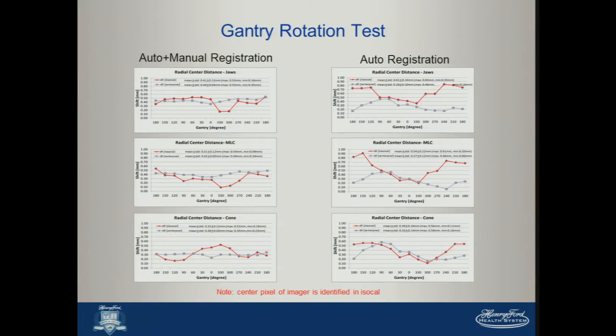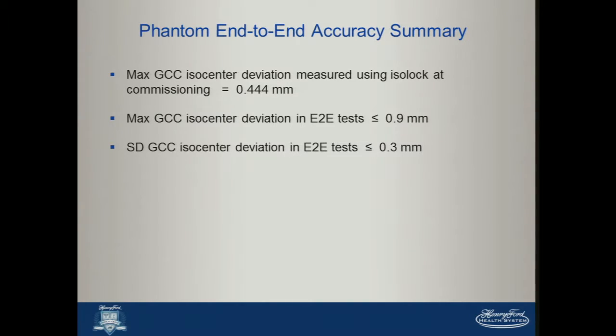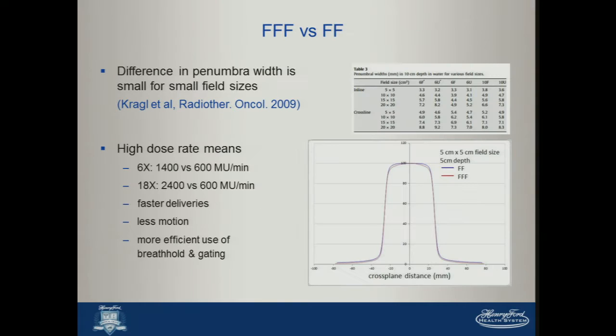So the end result is that we had at commissioning and continue to maintain pretty tight specs on this particular delivery platform. Max isocenter deviation accounted for gantry, collimator, and couch is less than 0.9 millimeter, with the standard deviation around about 0.3. So in case you're interested in comparing as you go into your own commissioning, I thought I'd report those figures. So, getting on to the flattening filter-free, the benefits of flattening filter-free modes in particular.